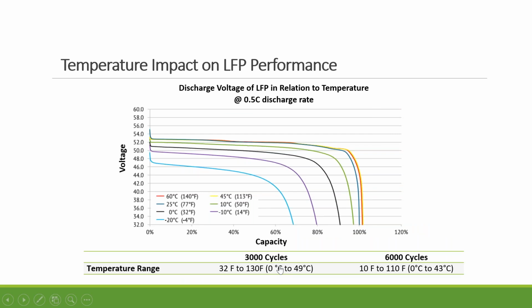When we talk about a battery's lifespan, there are always three main factors. One is the charging and discharging rate. Typically we suggest setting it at 0.5 C. That's really good for the battery lifespan. Just to give you an example, if the LFP 10 is 200 amp hour, then 0.5 C is 100 amp. So the charging and discharging rate is 100 amp, and you can set that up in the BMS.